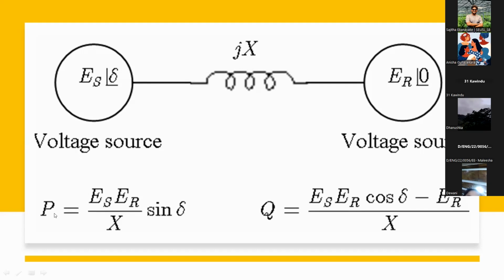Active power flow is given by this equation, and reactive power flow is given by this equation. The important thing is that active power flow depends on ES, ER, and X - these are voltage magnitudes, and X is the impedance. The much more important thing is this delta. These magnitudes are just positive values, and delta is the angle difference of the two voltages.